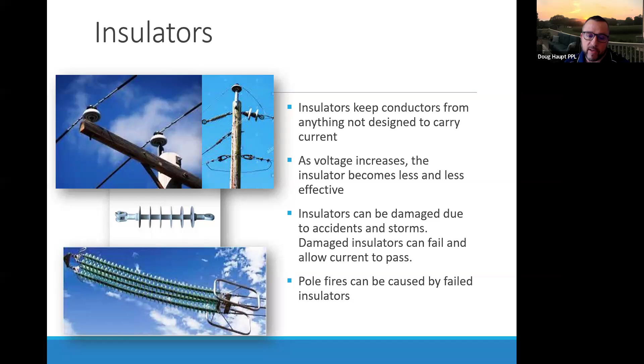You can see the distribution insulators versus this larger string of insulators on a 500 kV line. That insulator string is about 22 feet long to stop the flow of high voltage out there on the transmission system. So just insulators and what they do.